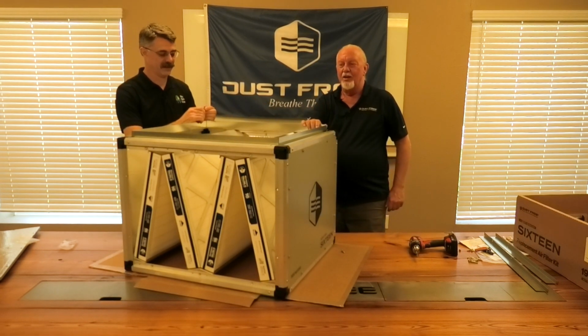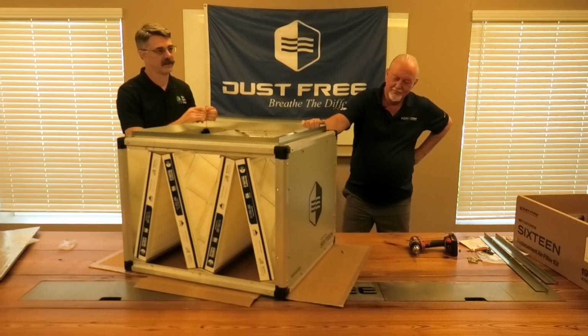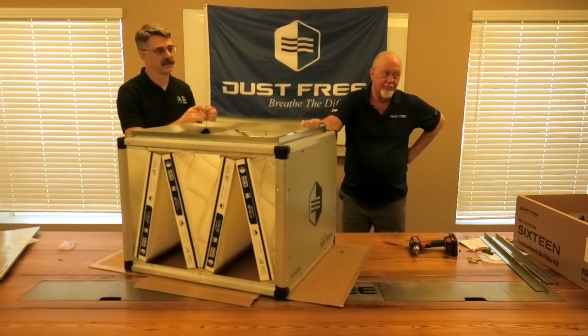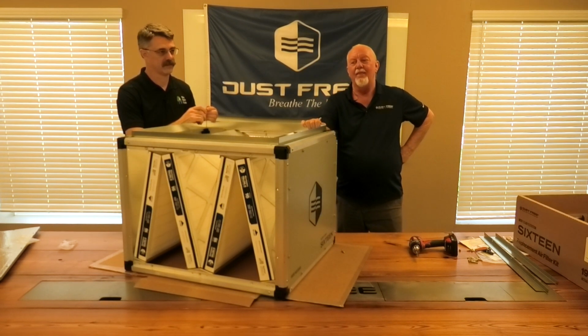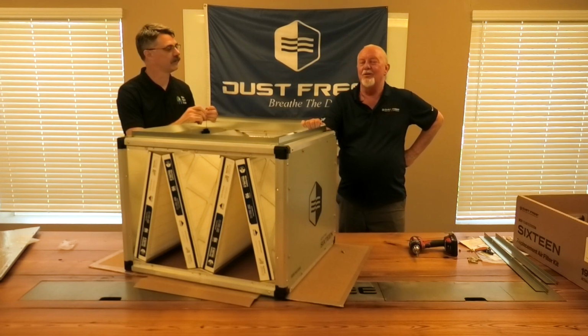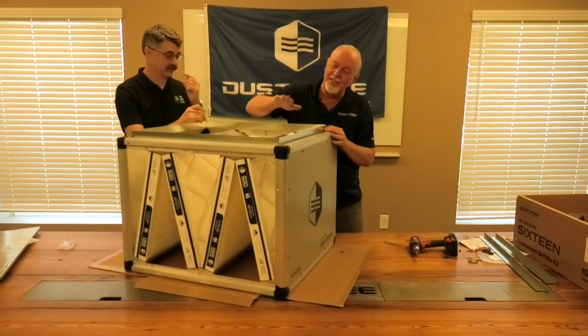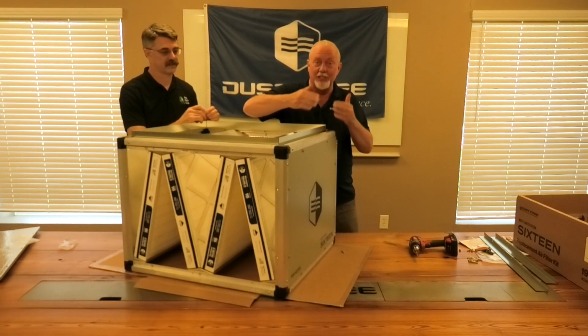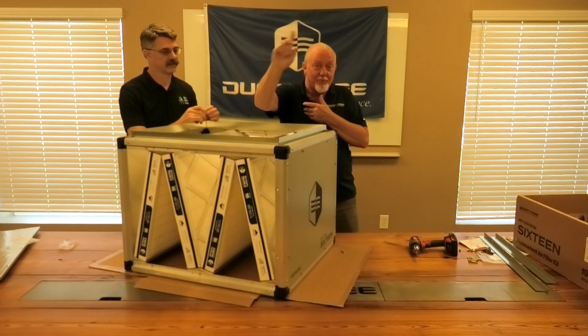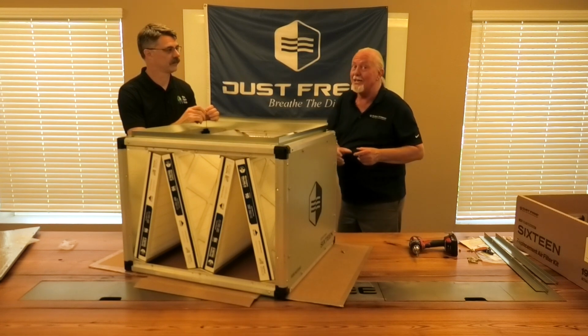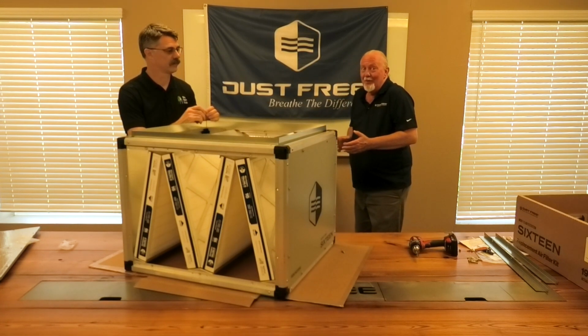As far as installation location, just make sure in front of wherever your filter access is going to be, you have at least the depth of the filter, which is 27 inches, so you need at least 28 inches to slide it out.